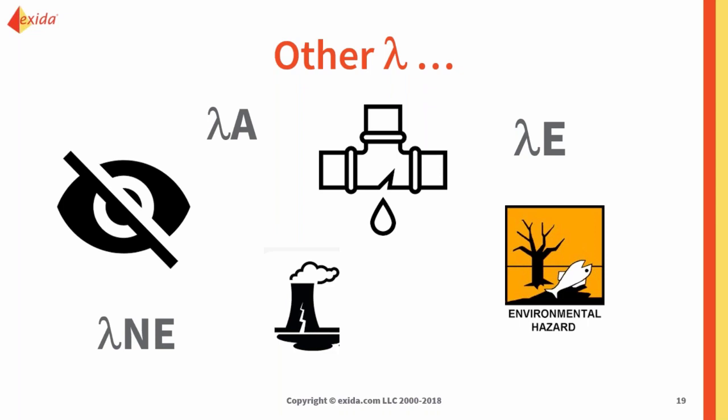Just like safe and detected, annunciated failures can be further broken up into subclasses of detected or undetectable if diagnostics are looking for those direct failures. The next failure rate we want to look at, let's look at NE or no effect failures. Sometimes they are referred to as residual failures as well. But those are failures that, once again, have no direct consequence on your safety function. So your safety system can still do its job. These, just like the annunciated failures, are often expressed in units of FITs, and all the annunciated, no effect, and external leaks can all be given to you through FMEAs.